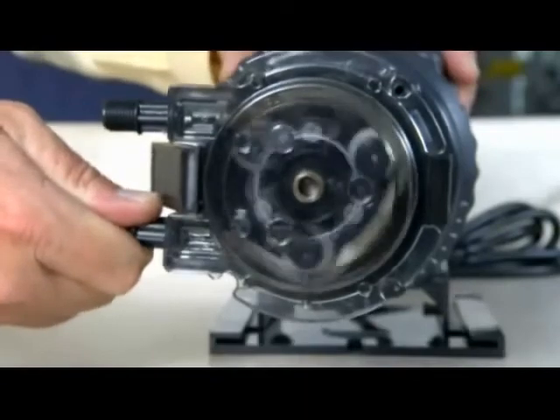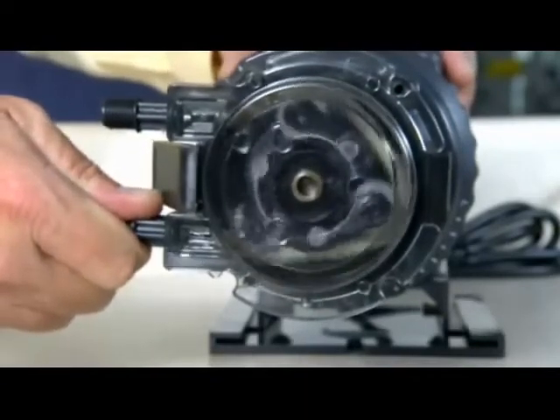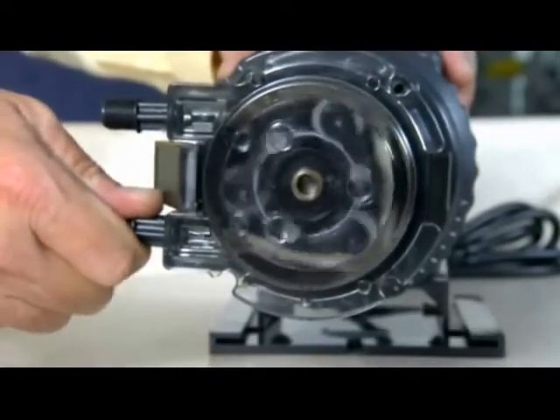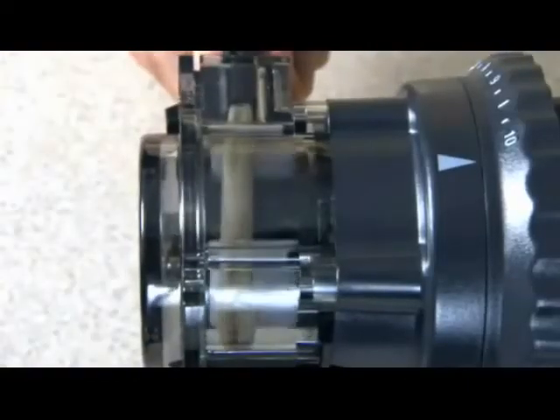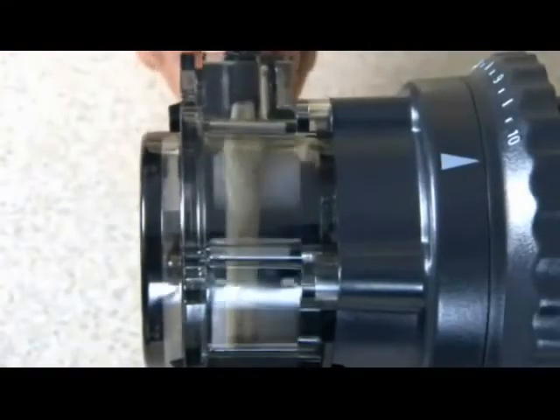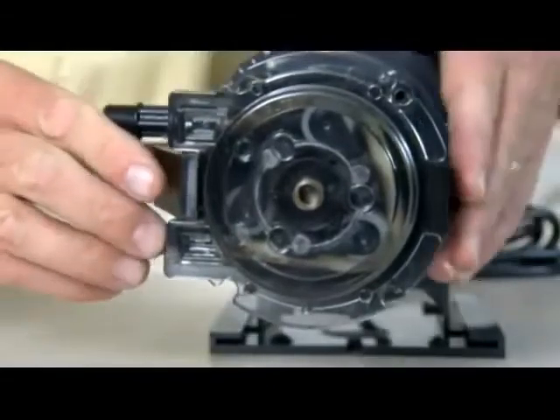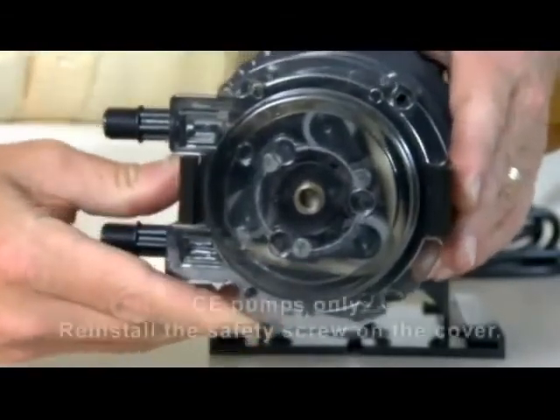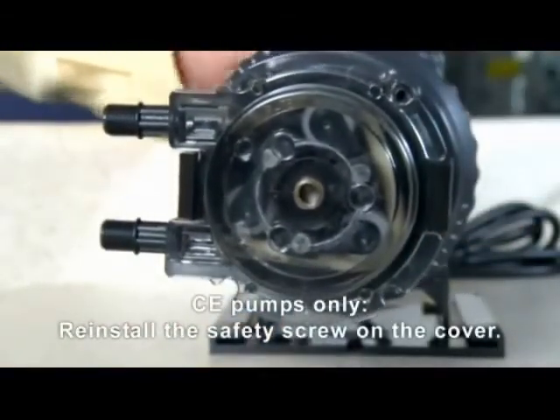Turn the tube fitting on the suction side, not more than 1/8 of a turn in the direction the tube must move. Do not let go of the fitting until the tube rides approximately in the center of the rollers. Turn the pump off. Let go of the fitting and secure the latch between the fittings.